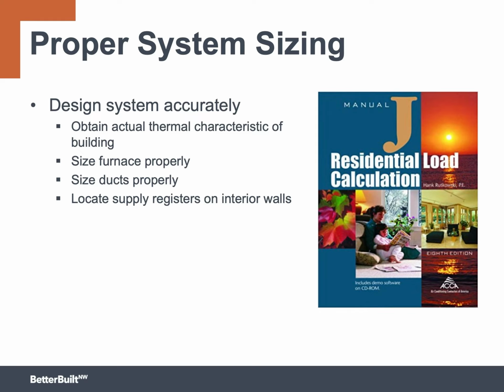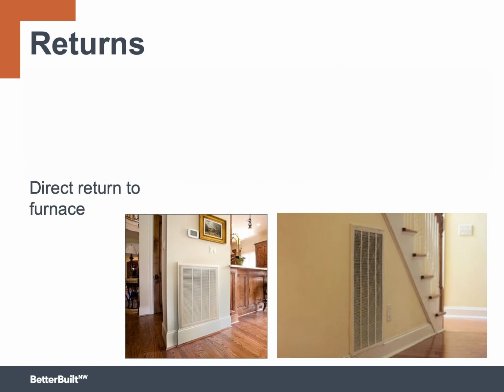With energy-efficient homes, especially with the ducts inside conditioned space, the thermal characteristics of the building will be much different. It's essential to perform an accurate calculation. This includes the insulation levels, window performance characteristics, and the building air leakage rate. And don't forget some of the basics, such as selecting the correct climate zone for the project. With proper inputs, the size of the heating and cooling system will be accurate, the system will function properly, and the occupants will be comfortable.